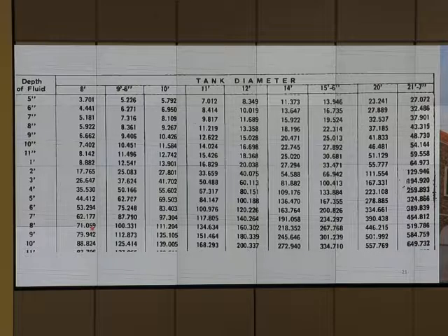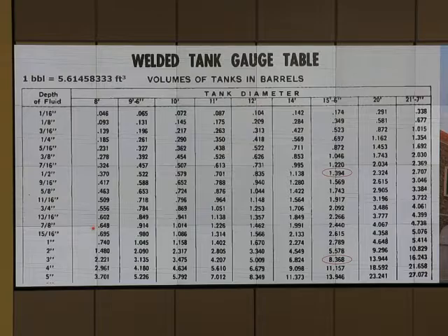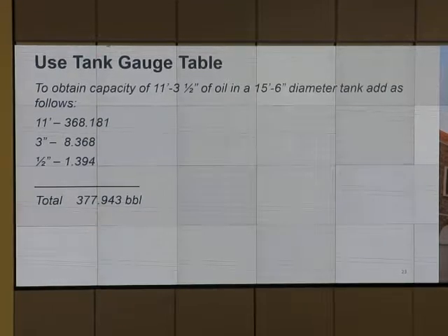Okay, good. Do you know how to get the number in the table? You're probably not the one who reads the table, but maybe the one who made the table, right? Just calculate the volume and put the number in. There's another name for that table too. Yeah, strapping table. When you strap a tank, you measure the diameter of various pieces up there so you can get the gradings. Okay, that's the table that we put in.